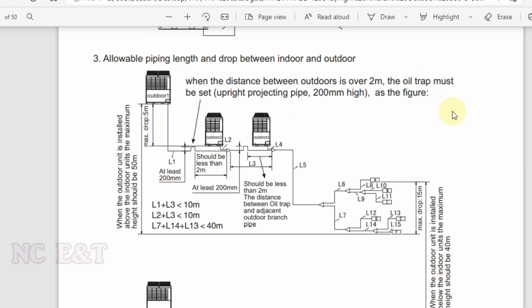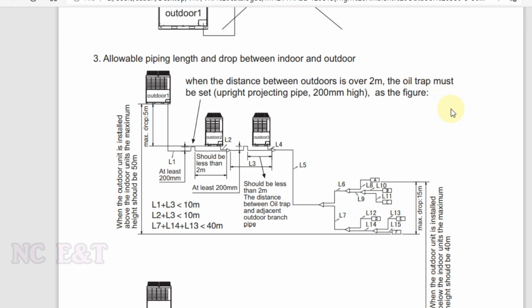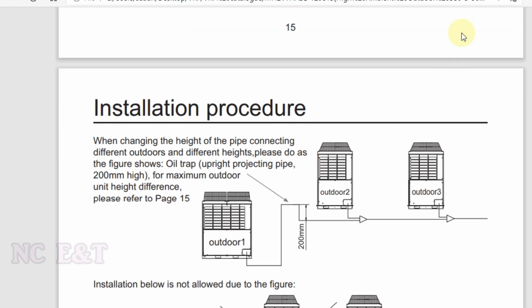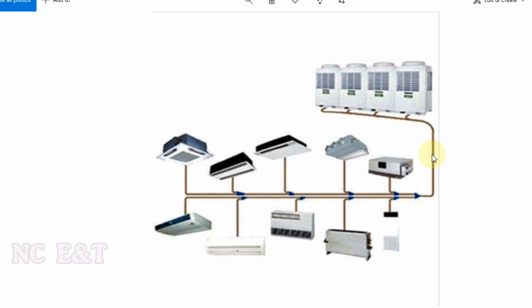Also, if we place the outdoor units away from one another by more than 2 meter, we need to provide the same type of oil trap in the piping connecting these two outdoor units, and the height of this oil trap should be minimum 20 centimeter as we saw before. These are the points to be considered during the installation. So in our study, first we have seen how to select the circuit for the VRF system, then how to select the pipe diameter of the VRF system, and what are the main points to be considered during the installation of the VRF system.